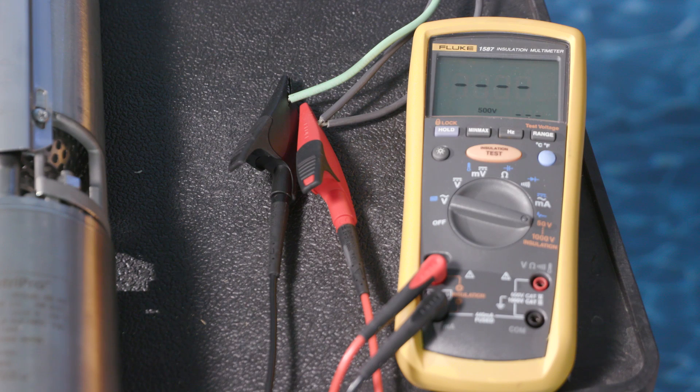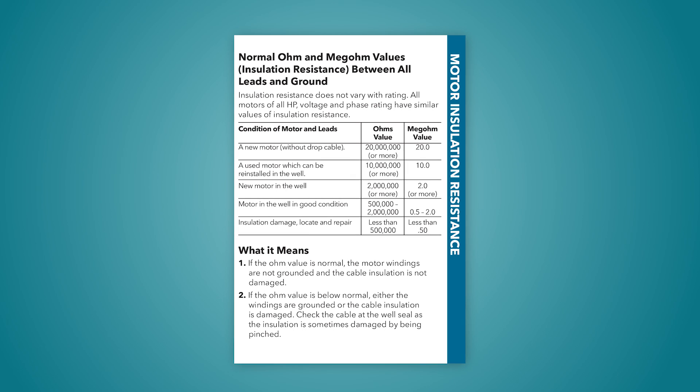To measure line-to-ground resistance with a digital insulation resistance meter, or Megger, again ensure there is no power to the motor. First, set the appropriate DC voltage on your meter. Use 500 volts DC for Goulds Water Technology products. Then, measure the resistance between each of the leads to ground. Compare the actual measurements to the normal ohm and megohm values chart in the pocket service manual, and determine the meaning of the results.